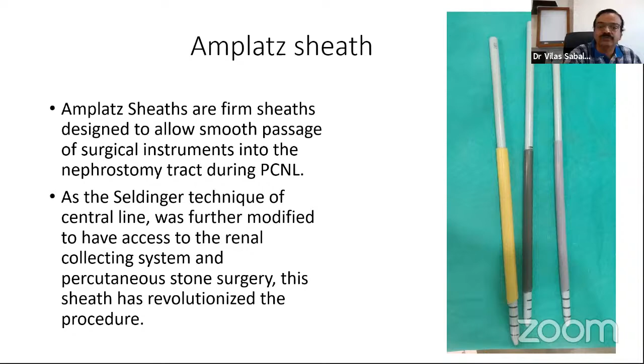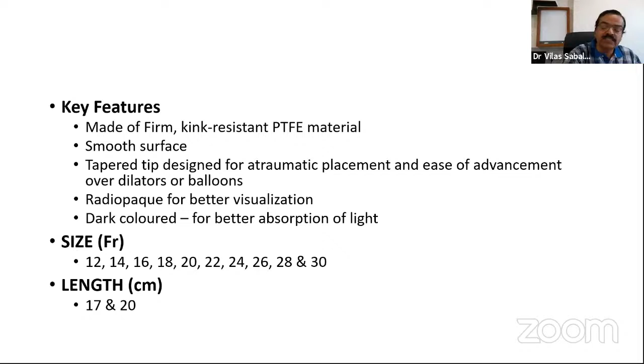The main features of Amplatz sheath: it is firm, kink resistant PTFE material. The surface is smooth. The tapered tip is designed for atraumatic placement and ease of advancement over dilators or balloons. It is radio opaque, though not densely radio opaque, but just to visualize it under contrast. They are usually dark color so as to absorb light rather than reflect it. Initially, the original set of Amplatz dilators with sheath was available only beyond 24 French. Now they are available from a smaller size, and the metallic are much smaller also available. The common lengths available are 17 and 20 centimeter Amplatz sheaths.